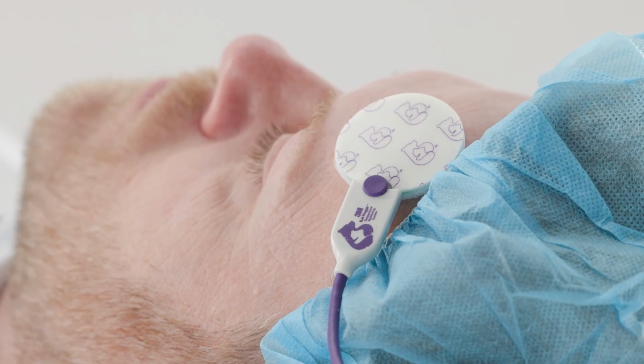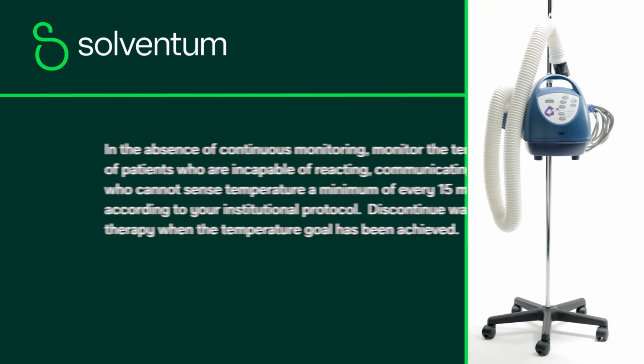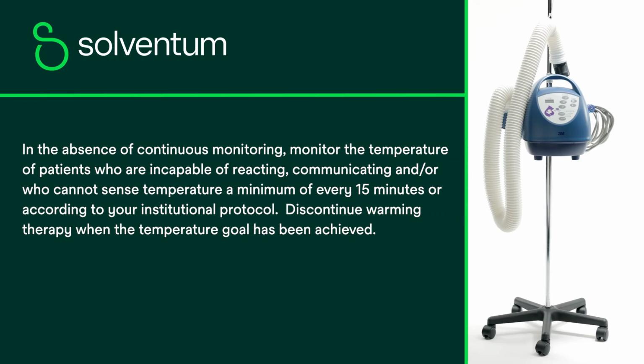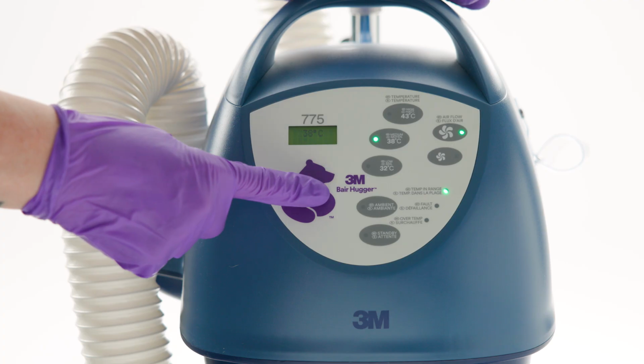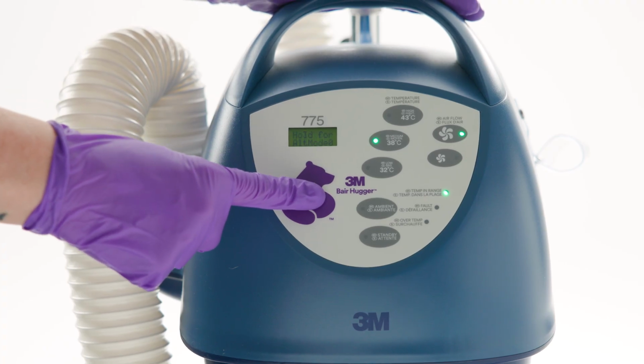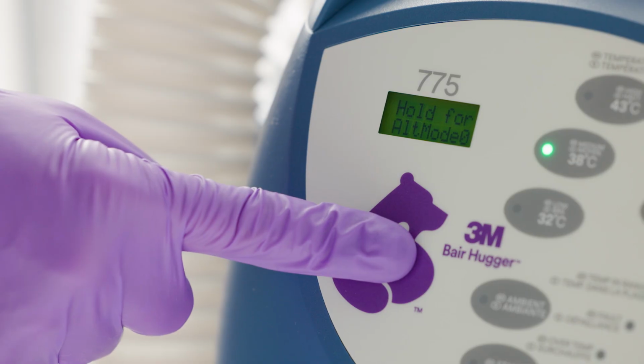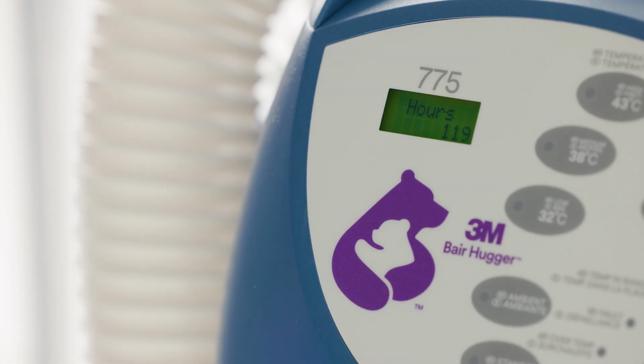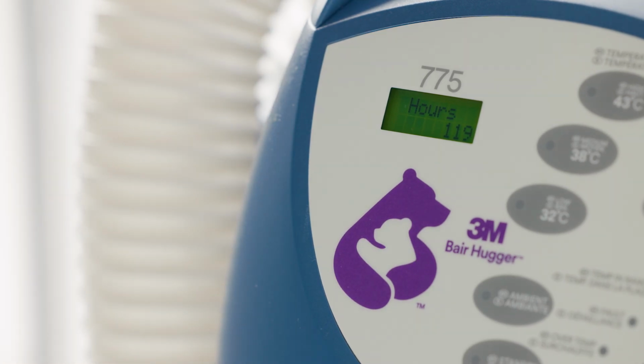Solventum recommends continuously monitoring core temperature. In the absence of continuous monitoring, monitor the temperature of patients who are incapable of reacting, communicating, and/or who cannot sense temperature a minimum of every 15 minutes or according to your institutional protocol. Discontinue warming therapy when the temperature goal has been achieved. To view the temperature mode timer, press the button and hold for 3 seconds for the current temperature mode. The display will show the temperature mode time, and then return to the temperature mode setting.